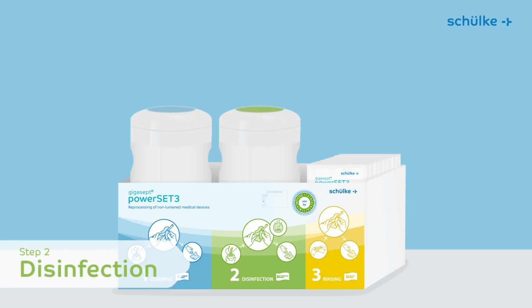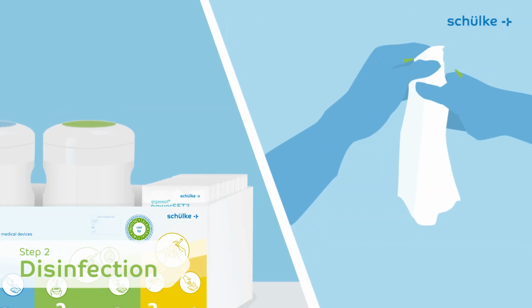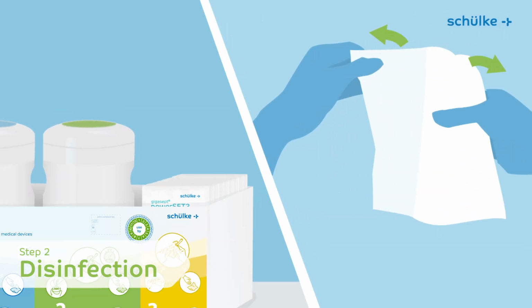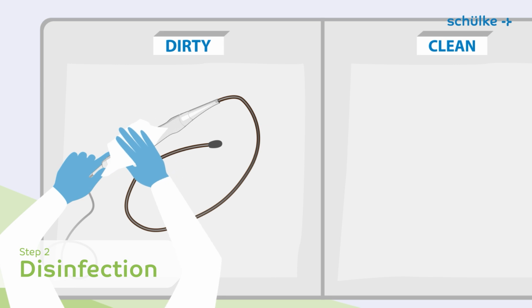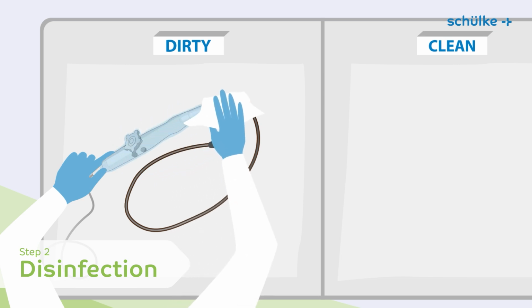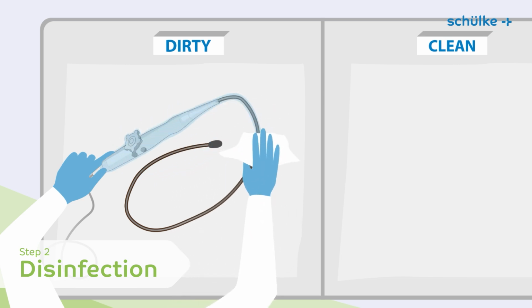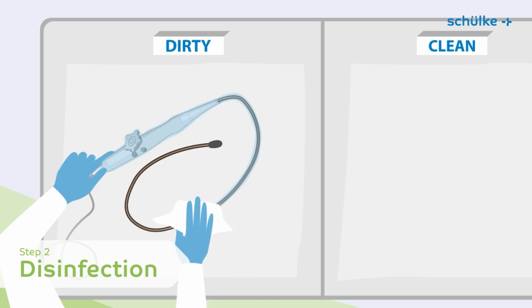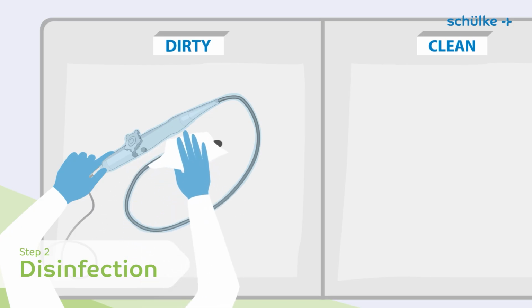The second step is high-level disinfection. Open the tub of gigasept powerSET3 disinfection wipes. Take out one wipe and close the tub again. Unfold the wipe. Wipe the medical device thoroughly from proximal to distal. Ensure that all areas are evenly and completely wetted so that all surfaces have a slight film of moisture.